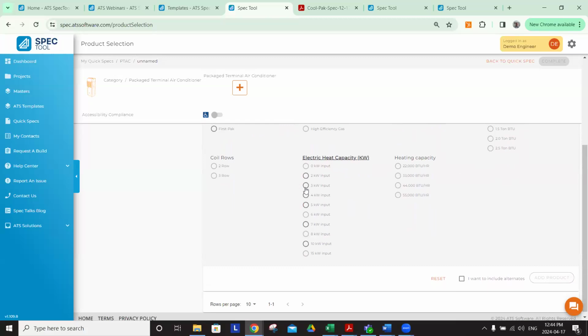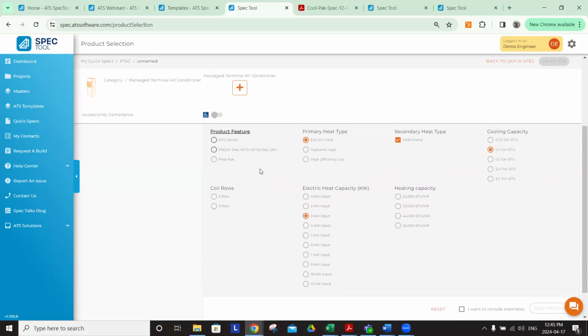And then your electric heat backup. Let's say 3 kilowatts. Yep, that sounds good. So now that we've chosen electric heat, we can't choose how many hydronic coil rows we want, and we don't need to worry about heating capacity. We've covered that in the kilowatts. The only selection left is, do I want the Eco Series or the Fresh Pack with the ERV built into it? That's the last choice to decide which unit you're going to put in.